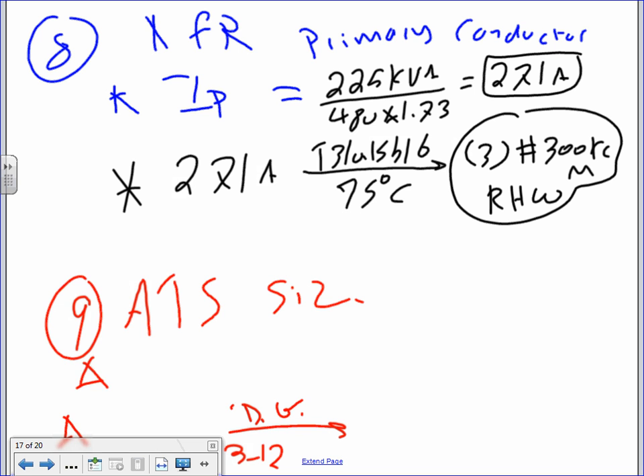The ATS the same way, guys. The ATS right here. So I take my conductors. What's my conductor? You take your 271 amps. It's already taken into consideration. Take it to the 3-12. And what's the next standard automatic transfer switch size? 300 or 400? 400. Yeah, 400. So we don't multiply it, 400 still the same, 400 here.